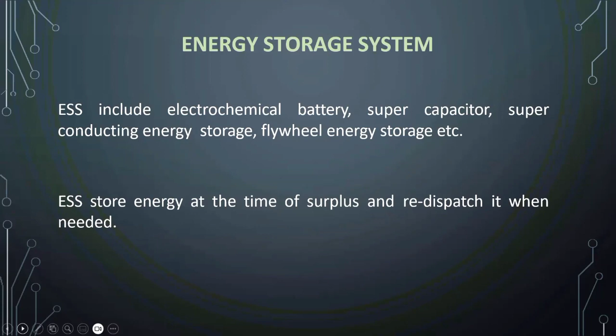Energy storage systems play an important role in the microgrid. The sizing of ESS is to be considered first when considering ESS in the microgrid. It's very important that first you need to know what will be the total load on the microgrid. After that, you should also know how much energy will be generated and can be stored, because it is very important that if you are trying to design a self-sustainable microgrid, then it should be on its own, not connected to the grid again and again.